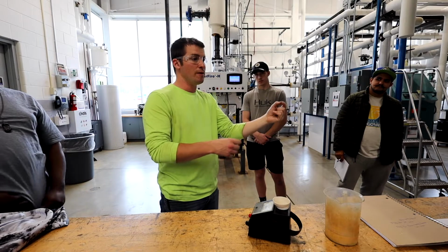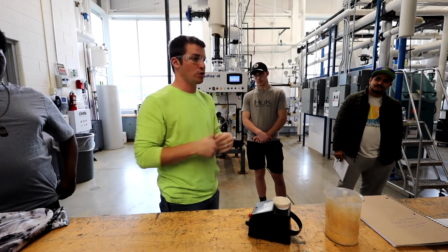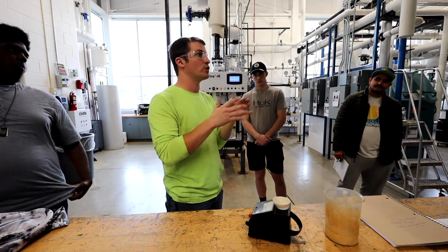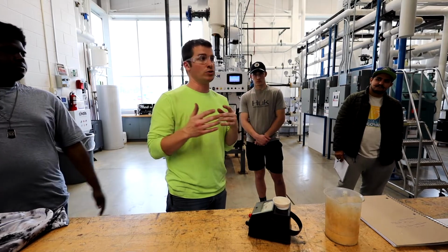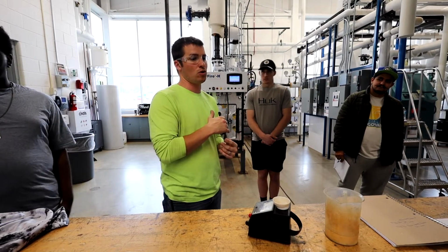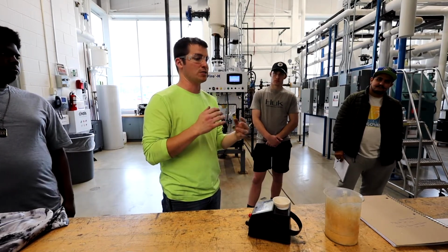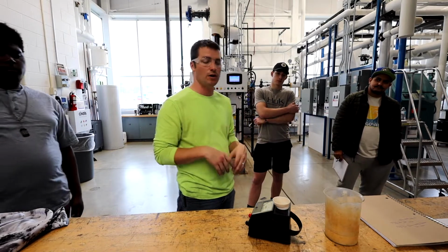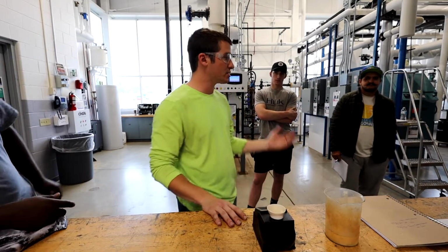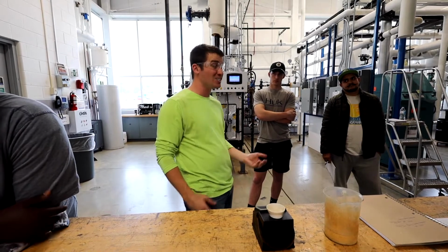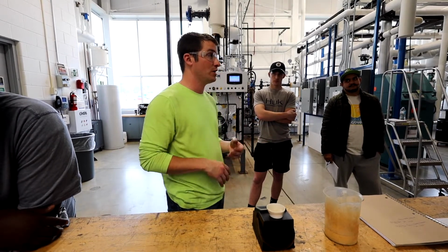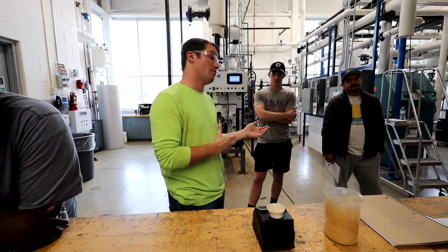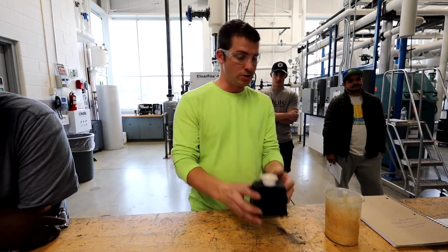So that's where you'll rely on your water treatment partner to kind of determine where you can safely run, that you're going to maximize the use of the water, but you're also gonna minimize potential issues from running too high, all right? So we always start with conductivity in a system because, again, in theory, if it's in range, everything else probably is going to be in range. If it's high, everything's probably going to be high. If it's low, everything's probably going to be low. All right? So this is a pretty simple test.